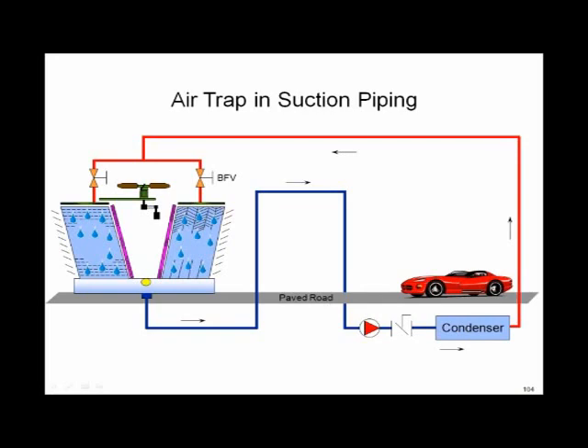As we did this over a period of time, we were able to get water up into that piece of pipe and get a lot of air out. Then we got the guy at the cooling tower out with that piece of plywood and turned the pump on at the same time, which is what we did. We yelled, got the plywood out of the bottom of the cooling tower, he jumps out, and we turned the disconnect switch, turned the pump on, and we called it flowing.